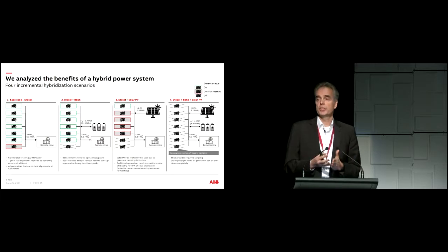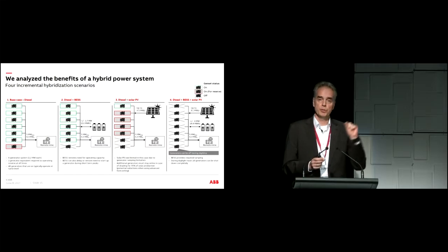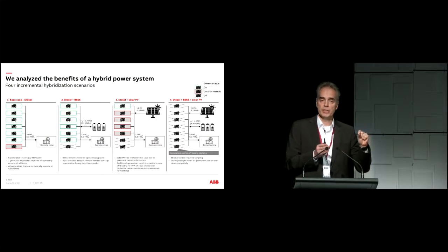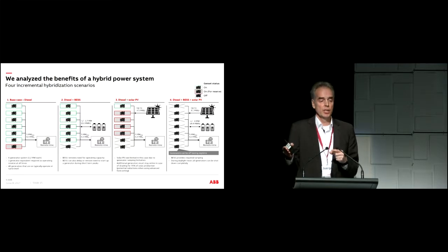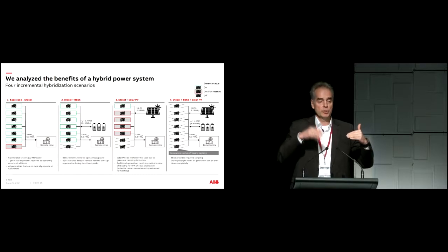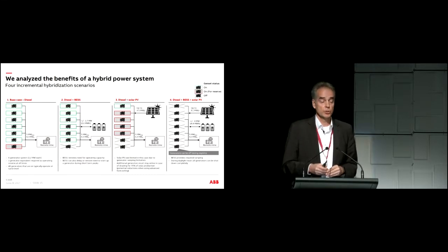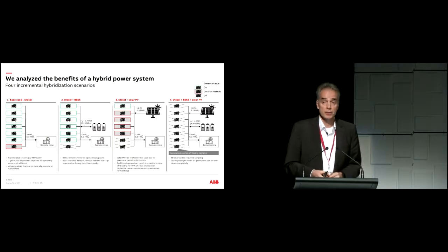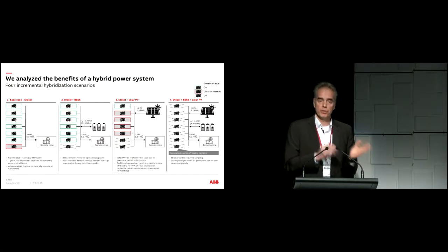The next interesting solution doesn't start with renewables, but simply adds storage to the existing diesel power station for spinning reserve. This means we can turn one generator off and use storage instead. If we see a loss of a generator, an increase in load, or just a peak, the storage system kicks in and discharges. If the peak goes away, we don't have to start another diesel, but if load has genuinely increased, we simply start another one. So here there's a business case, numbers coming shortly, that looks at spinning reserve with a diesel generator to create a return on investment.